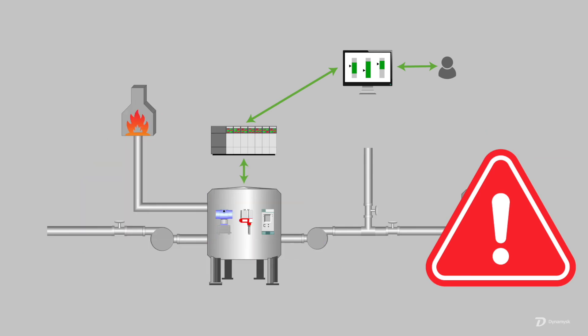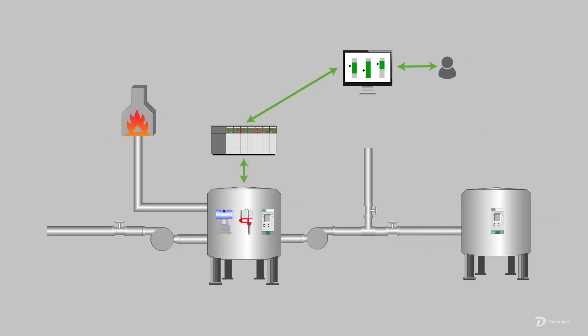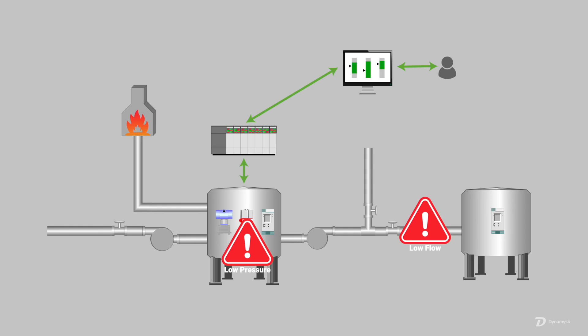When process systems start to cascade, alarm masking can be implemented. An operator doesn't need a pump tripped alarm followed by a low flow alarm followed by a low pressure alarm — all driven by the same pump stopping. At that point they need one alarm that says the pump has tripped, and the rest of the alarms in that process system can be masked. This is a more advanced application of digitalization where we can help the control system and operations, recognizing the scenario and prioritizing alarms appropriately.